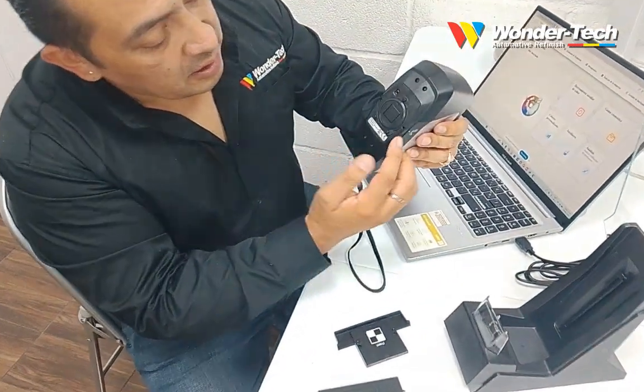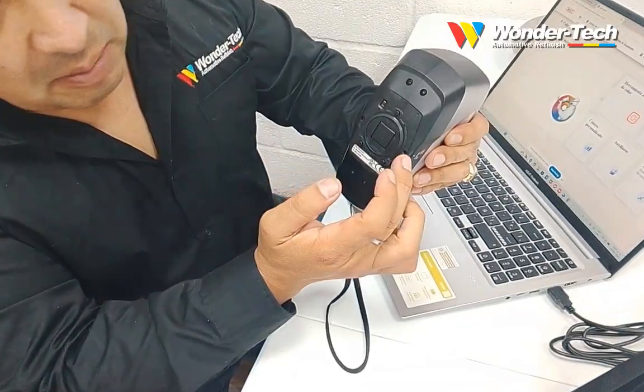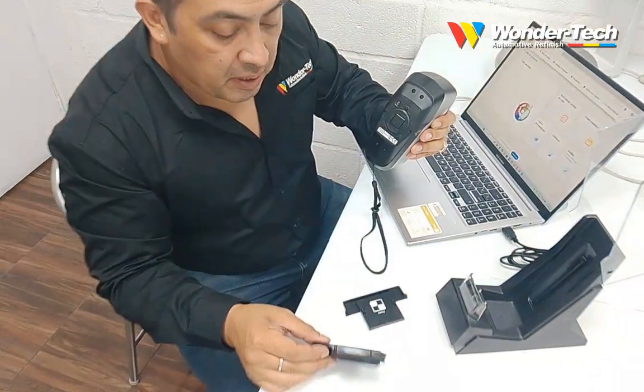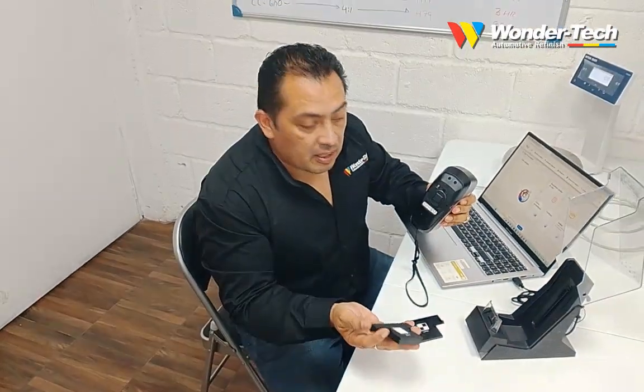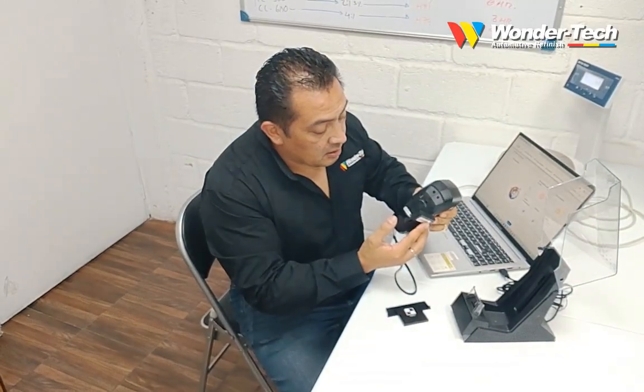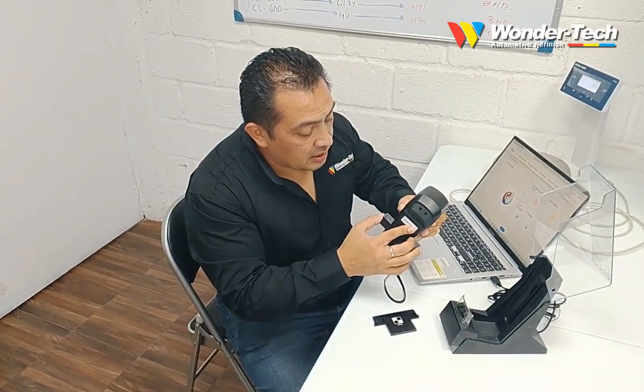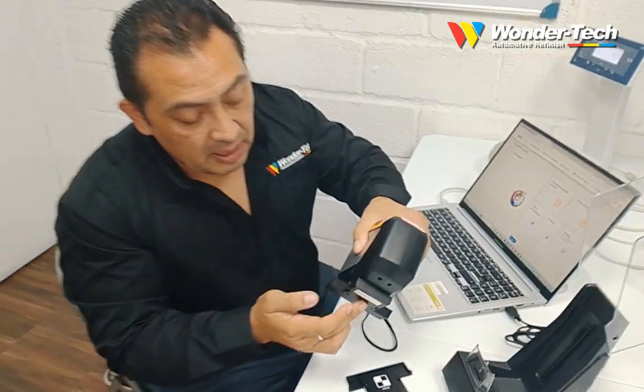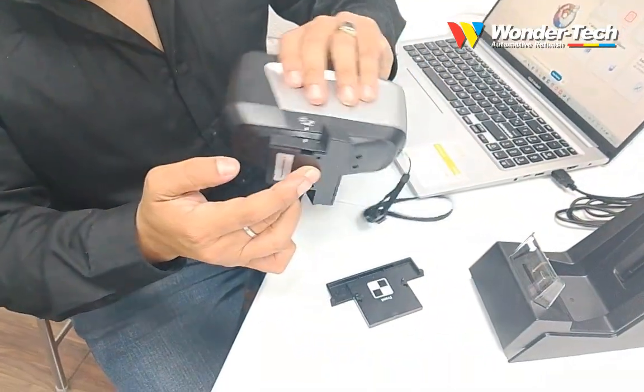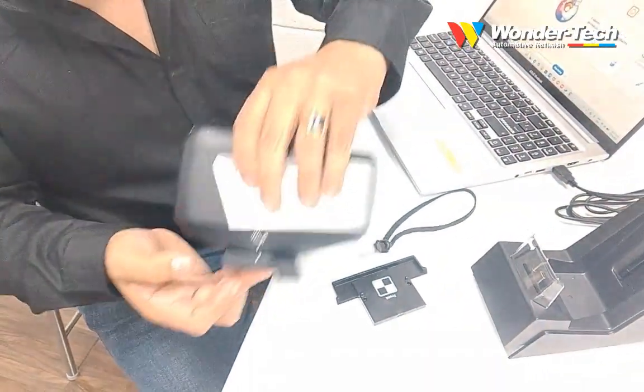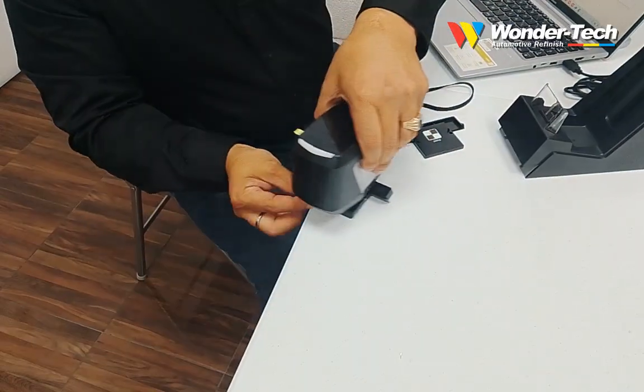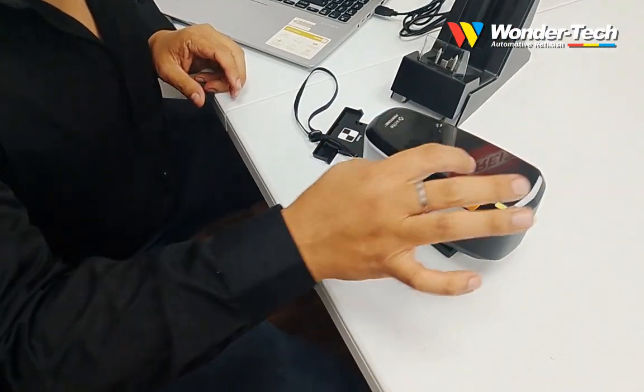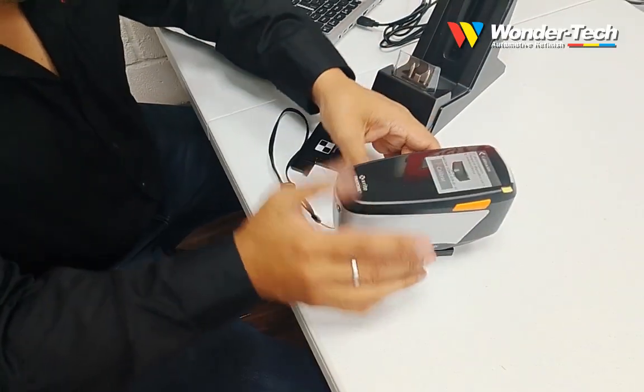I'd like to point out an important detail. Notice that one alignment pin is slightly larger than the other. The matching slots on the spectrophotometer are designed the same way. This ensures the calibration tile can only be inserted in the correct orientation. If you try to place it incorrectly, it simply won't fit. Both alignment guides must match properly.